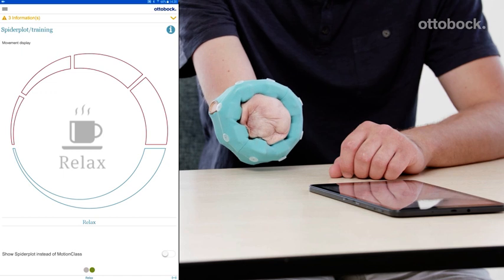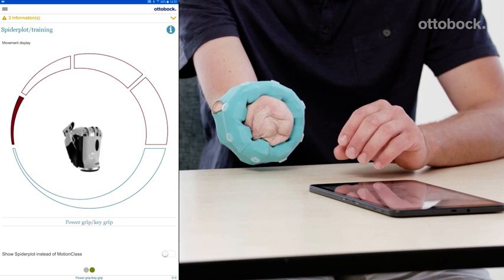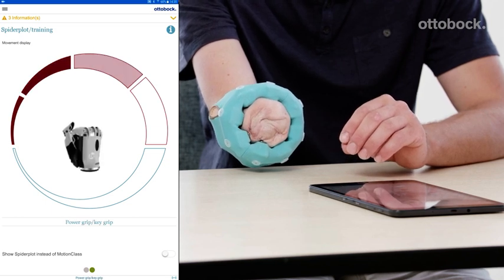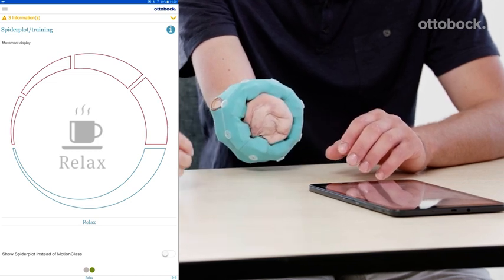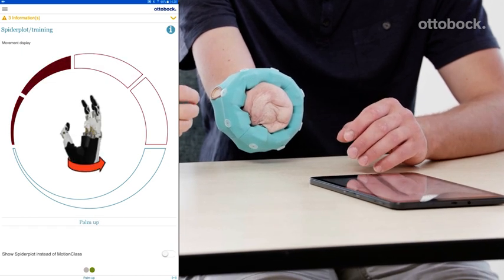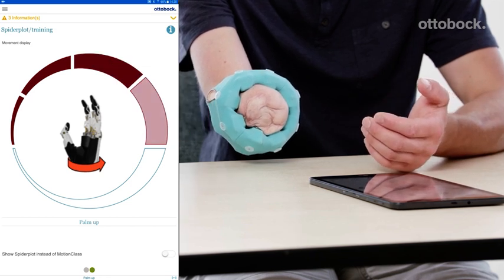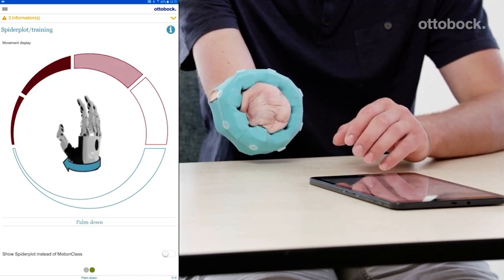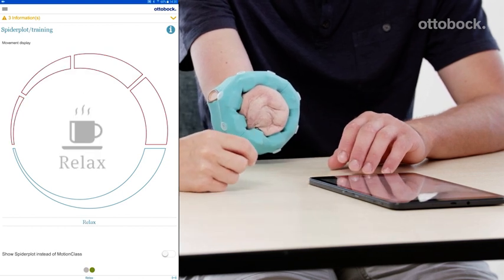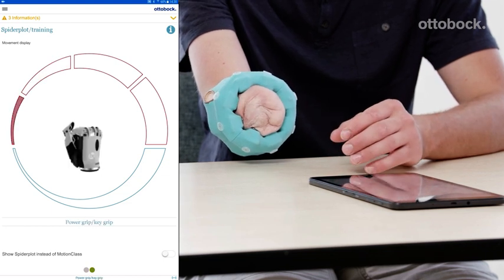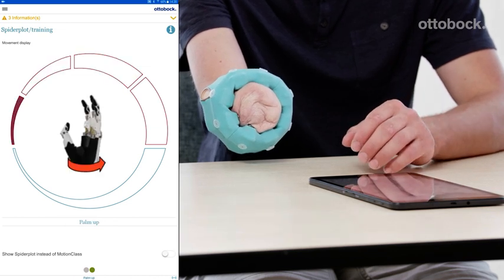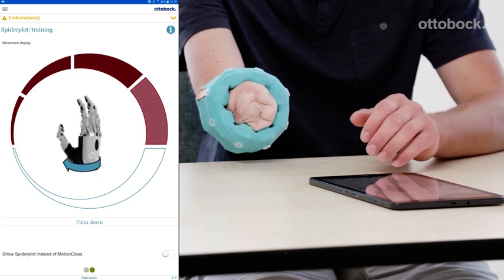If MyoPlus reliably recognizes the desired movements, use these phantom hand movements for the interims or definitive prosthesis fitting. If MyoPlus is unable to detect the desired movement, this can be due to two reasons. Reason 1: The movement patterns are too similar and MyoPlus cannot distinguish them. In this case, find alternative phantom hand movements and record a new test set. Reason 2: The user performs a different hand movement as recorded in the test set. In this case, encourage the user to perform the correct phantom hand movement. Note that this type of prosthesis control is a new experience for the user and requires effort in the beginning. If necessary, take a longer break before the test to prevent muscle fatigue.